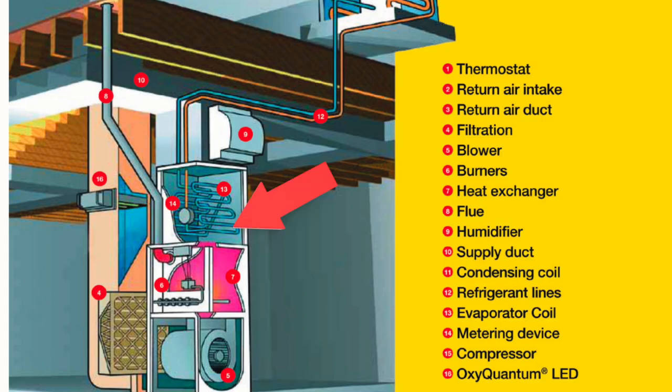Two possibilities. The first, primary and most probable cause is mold and mildew in the indoor drain pan associated with the indoor coil — the air conditioning coil. It's the one that's wet all summer long, running condensation from the air conditioner. We can get sludge buildup there, and when it dries out, it can take on a real stinky odor. So I'd most likely want to clean that indoor coil. A little household Clorox doesn't hurt a thing as a rinse after you clean it out. That's primary.